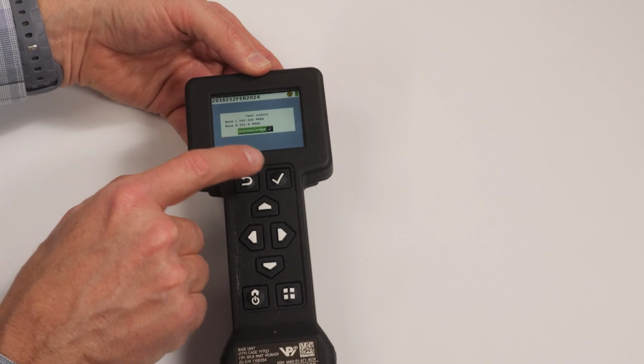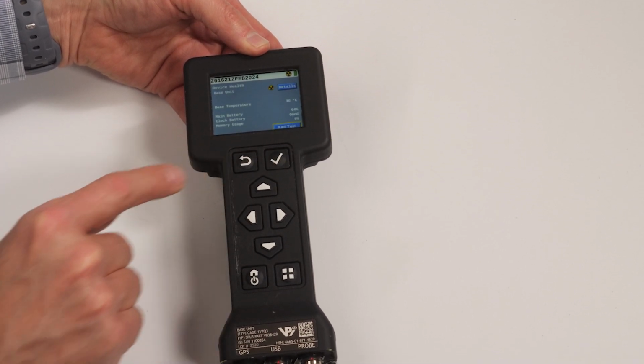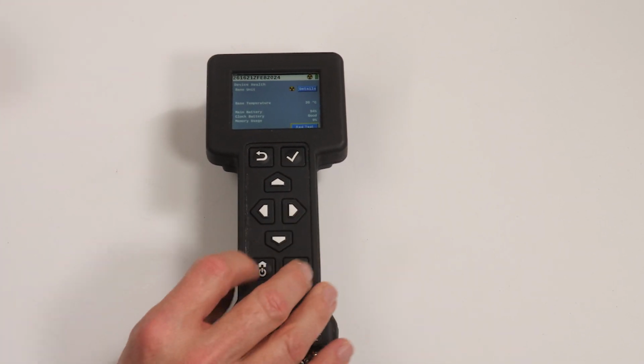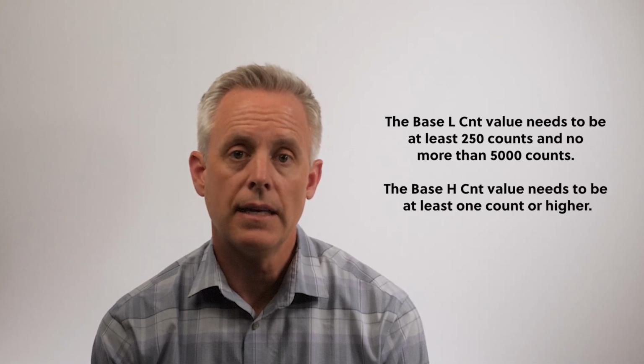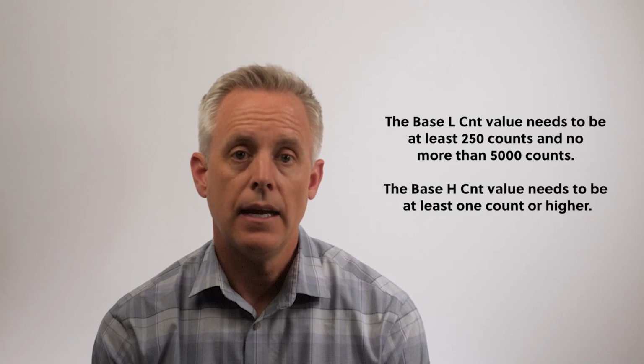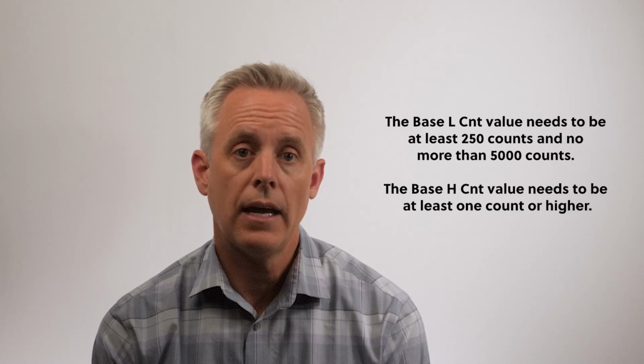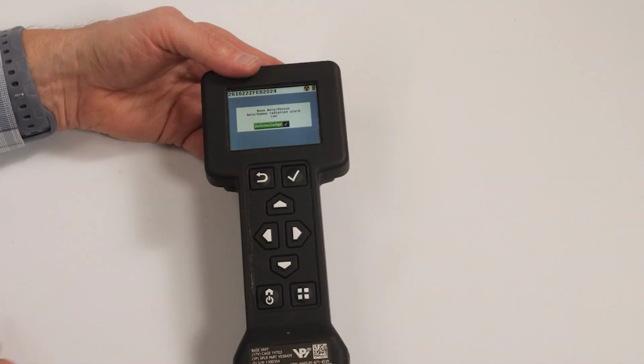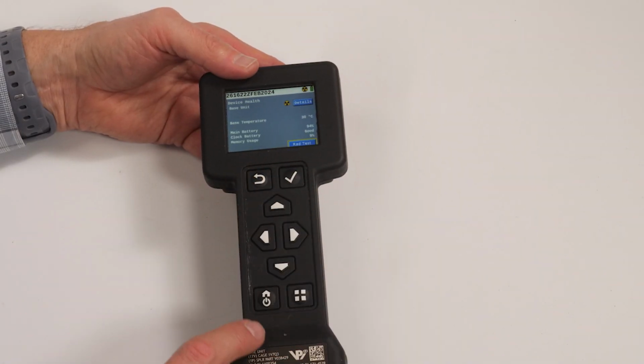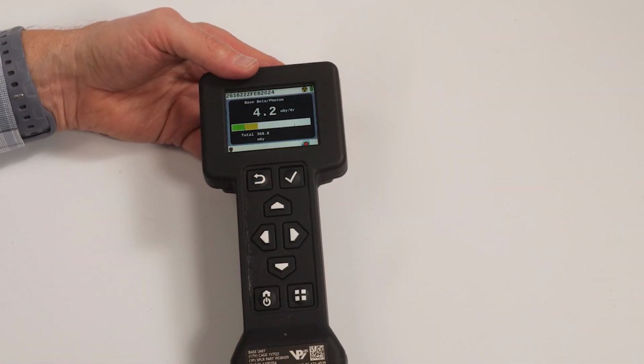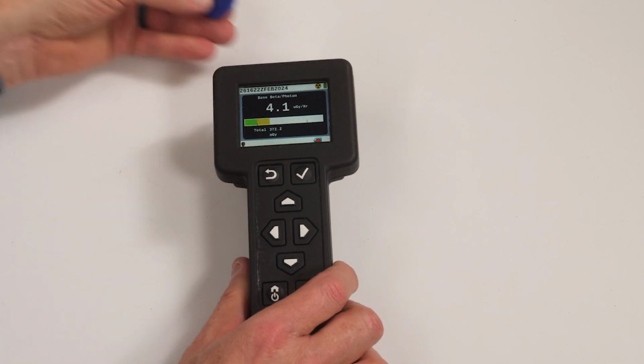Confirm that Pass is displayed within 1 minute of the check source being in place. You should also note the count values from the RAD test. The base L count value needs to be at least 250 counts and no more than 5,000 counts. The base H count value needs to be at least 1 count or higher. After 1 minute, you can press the Enter key to acknowledge and end the RAD test. After completing the RAD test, you are ready to conduct your survey or mission.